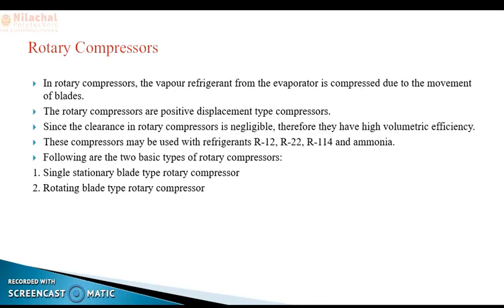In the rotary compressor there is no clearance volume, therefore the volumetric efficiency is very high. These compressors may be used with refrigerants R-12, R-22, R-114, and ammonia. The rotary compressor is categorized into two types: one is the single stationary blade type rotary compressor, and another is the rotating blade type rotary compressor.